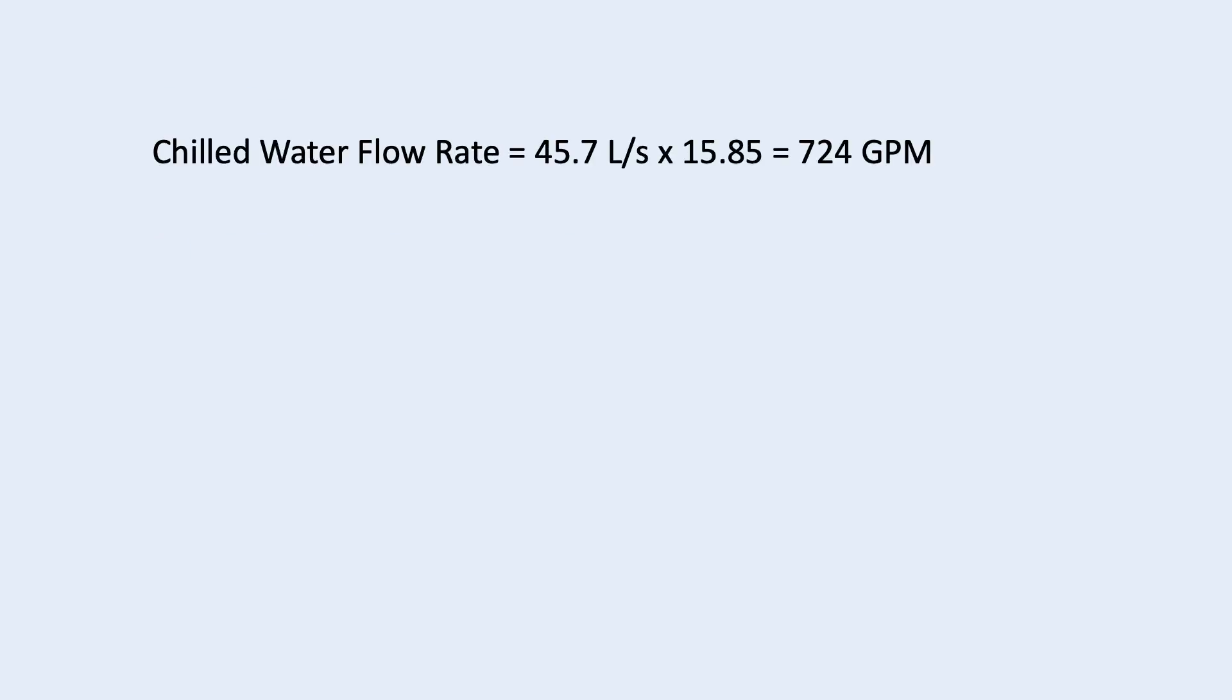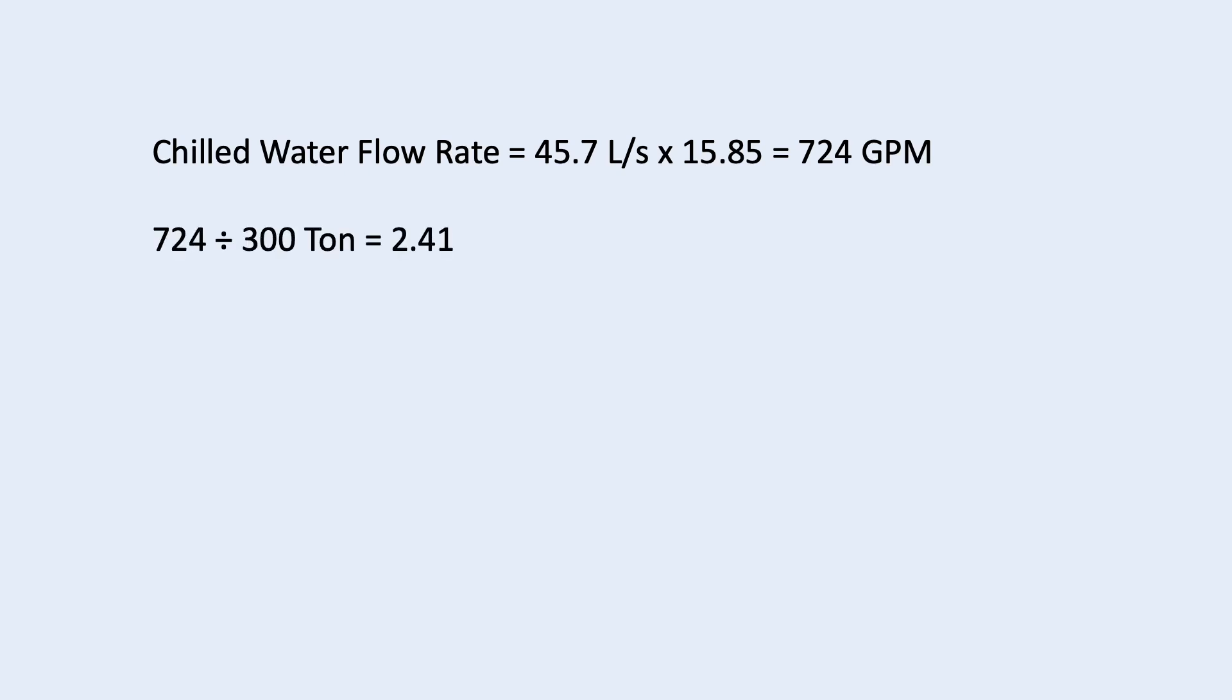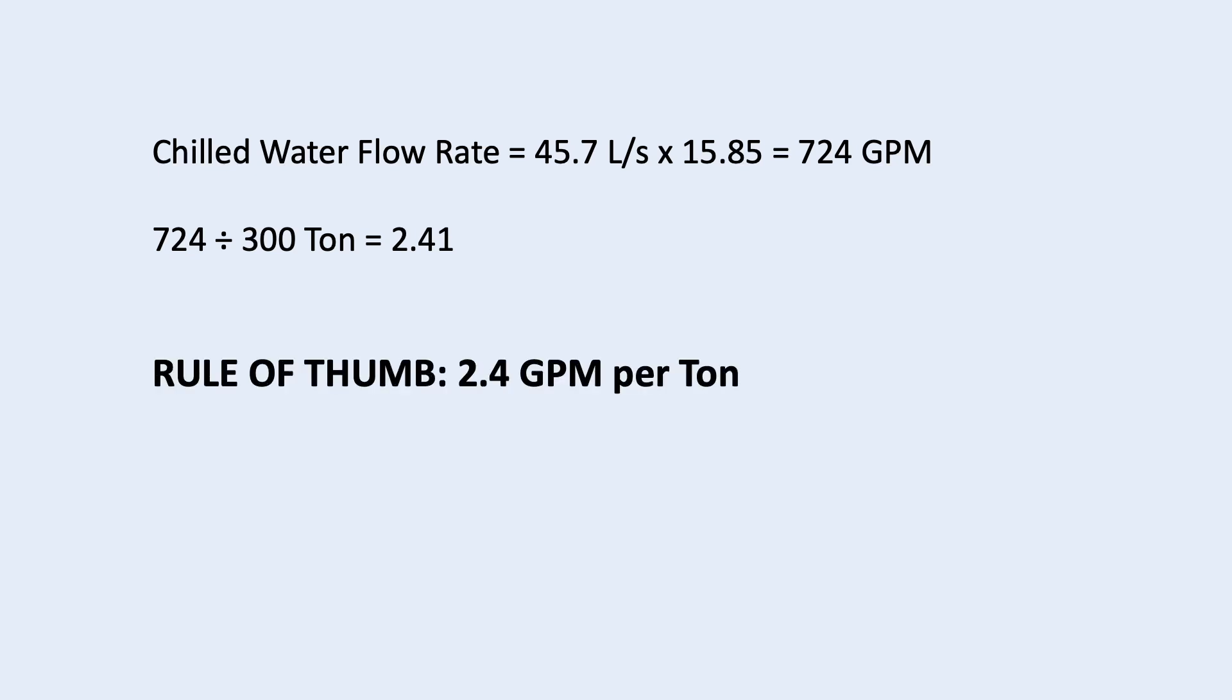If we take 45.7 liter per second and multiply it by 15.85, we will get 724 GPM, gallon per minute. Then, 724 divided by 300 ton is 2.41. So this is a quick way to calculate chilled water flow rate.